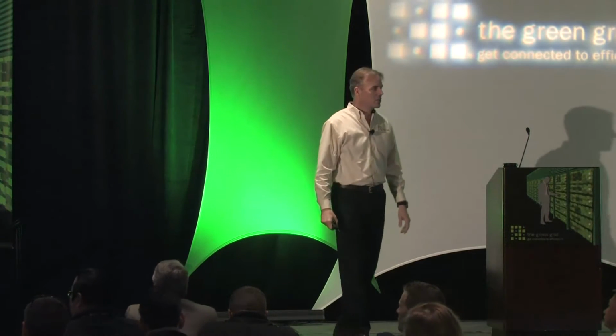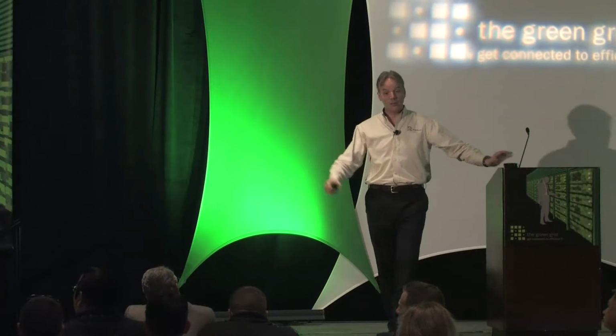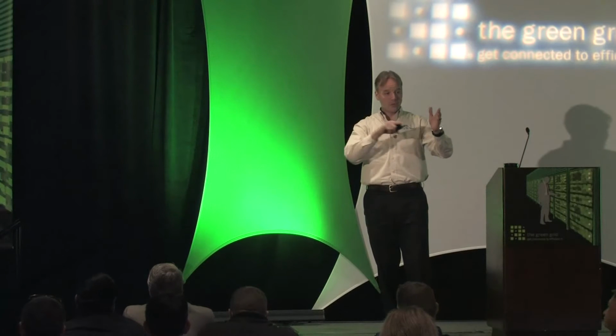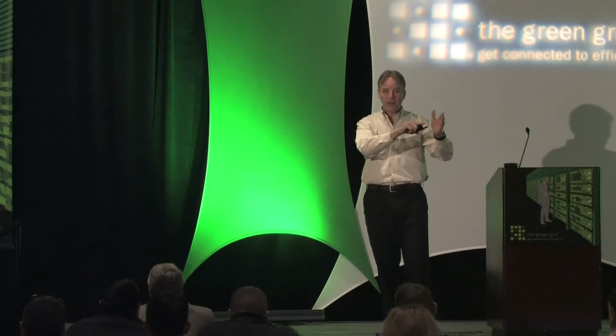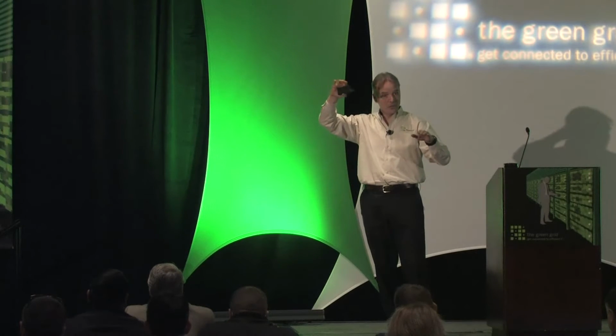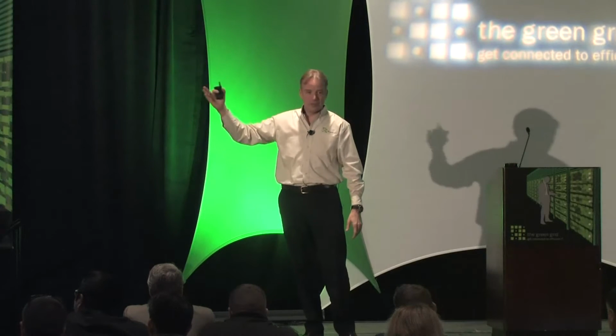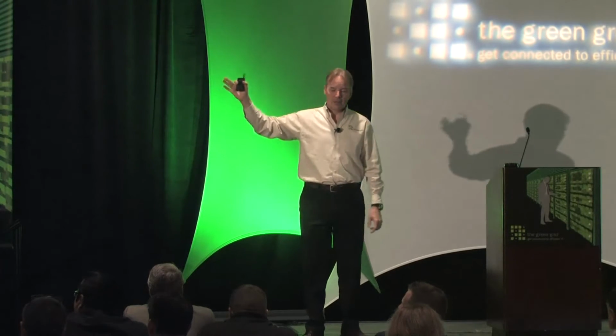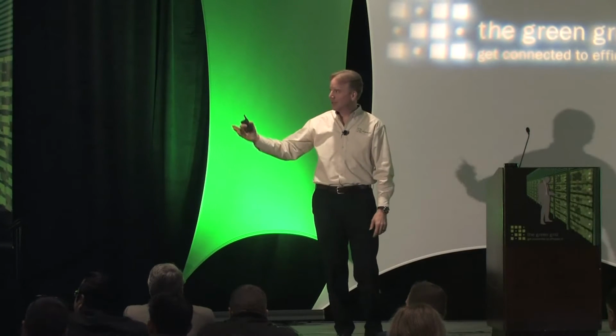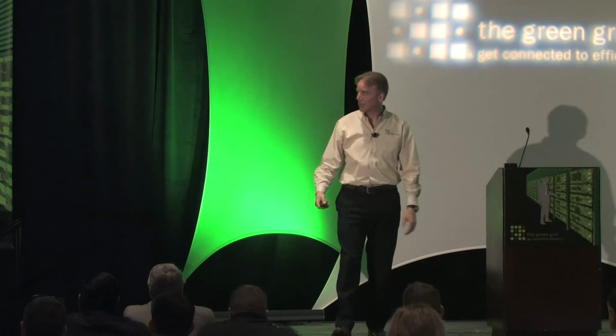And then having a target of less than 1.2 PUE average for the year. Okay? And also, they came back within the responses in these and the design. This is what PUE is going to do over a 12-month period, right? And also over a load period at 20% load, 30, 40, 50, and all the way back up to 80 or 90. Okay, so what we're trying to get to is a maximum of 1.2 at 80% load of our center. We're actually achieving that even closer to 35% load now. It's great when everybody aligns.